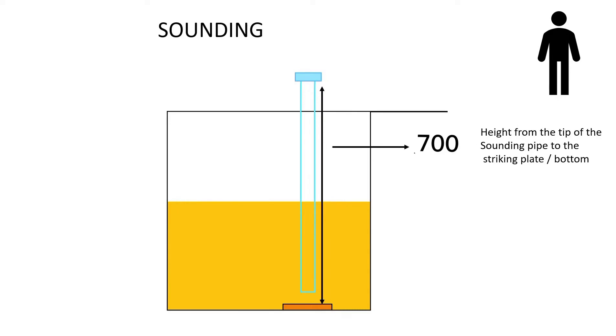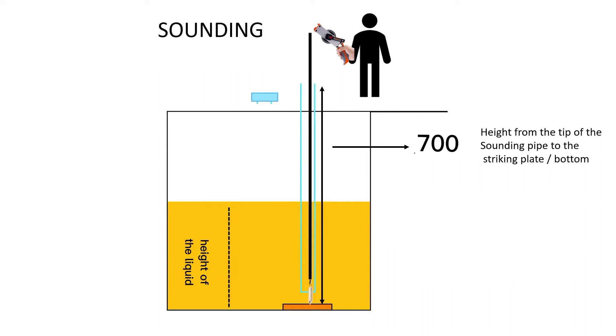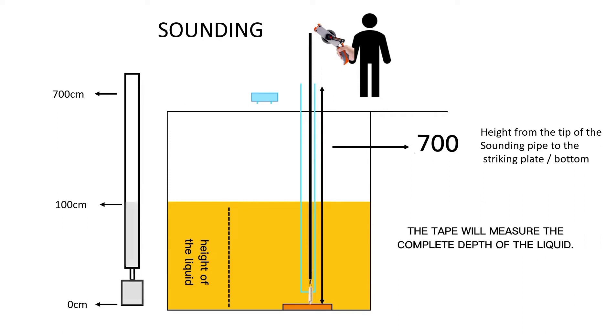Let's proceed, here we have a tank filled with diesel oil. The height from the tip of sounding pipe to the striking plate is 700 cm. A sounding method is used. First, remove the sounding cap. Insert the sounding tape to the sounding pipe and roll down until it touches the bottom of the tank or at around 700 cm of the tape. The tape will measure the complete depth of the liquid.